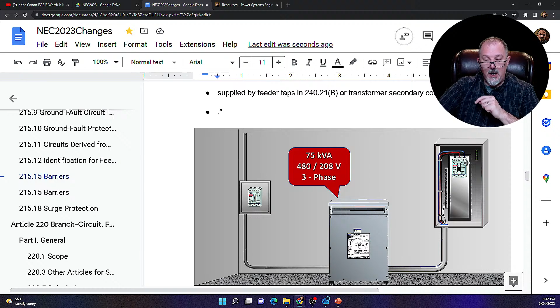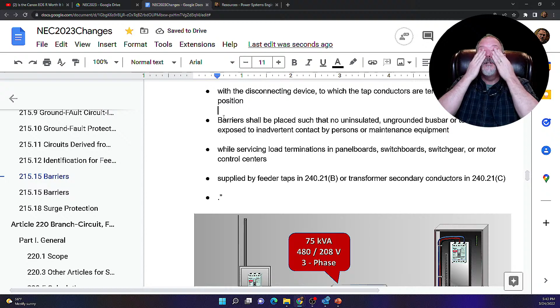Right? So while they're servicing load terminations in a panel board, switchboard, switchgear, or motor control centers. So if I am servicing the load terminations here and I turn this to the off position, I can't expose my electrical worker to shock, and I have to barrier off that line side termination. That's what that language is saying. So you have to rearrange it a little bit to really understand what we're saying in here.